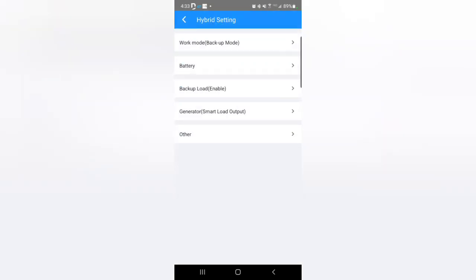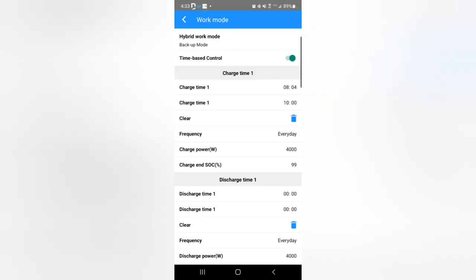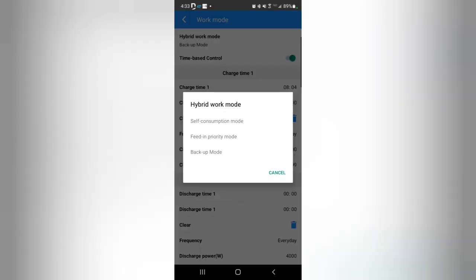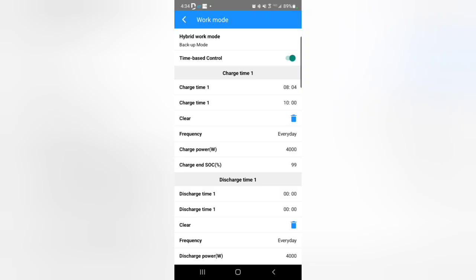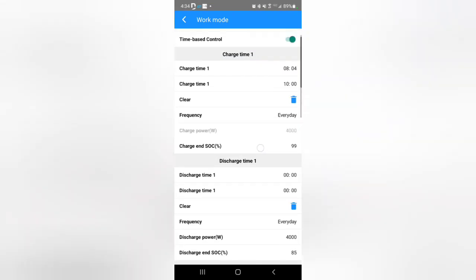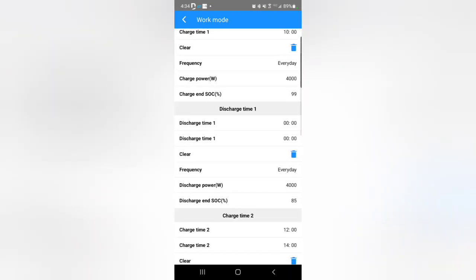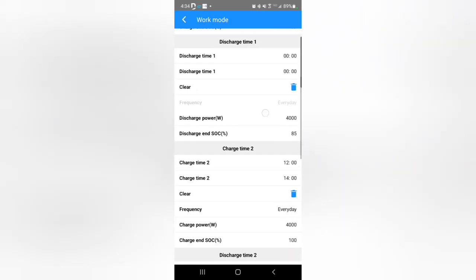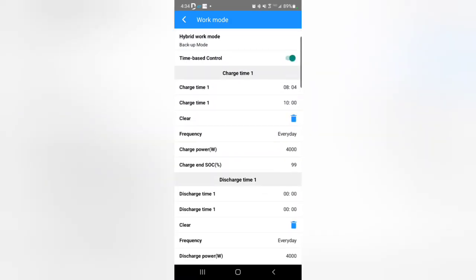Hybrid settings. This is probably where most of you guys will use stuff. Work mode. I have backup mode. You can do self-consumption mode, feed-in priority mode, the backup like I'm doing. Also with this, you can do time-based control. So I turn that on, and you can decide when to charge, and you can actually discharge your battery, set how much watts you want to, and discharge to like 85% is what I have on there. So just a couple settings that way, which is pretty handy to use.